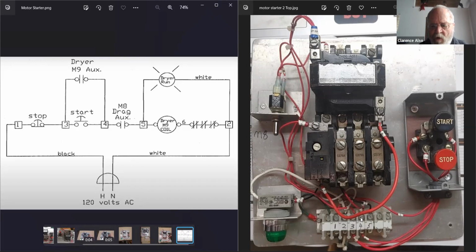So should I put it at 4 or 5, or on the interlock itself, the M8? I would put it on 4. Okay, you put it on terminal 4. Here's your probe, terminal number 4. What are you expecting there? 120. When are you expecting 120 at number 4?